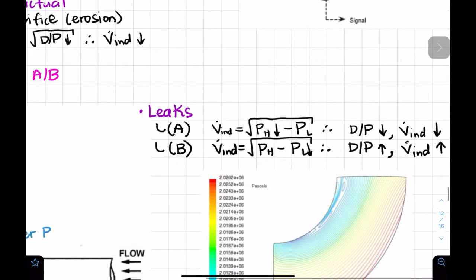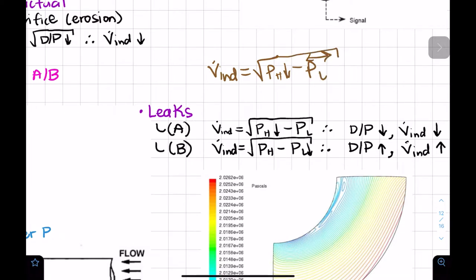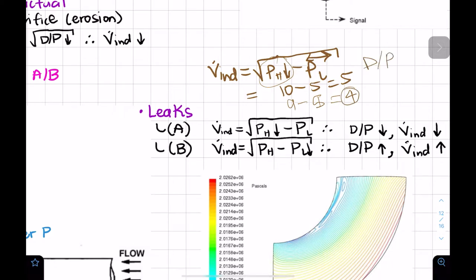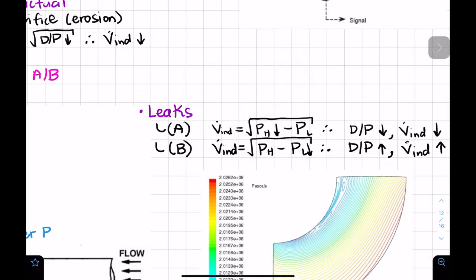As an analysis technique, I like to plug in fake numbers so I can get a sense of what's happening. For example, if high pressure starts at 10 and low at 5, and the high side decreases to 9 due to a leak while the low side stays at 5, then differential pressure drops from 5 to 4 — confirming the flow indicated decreases.